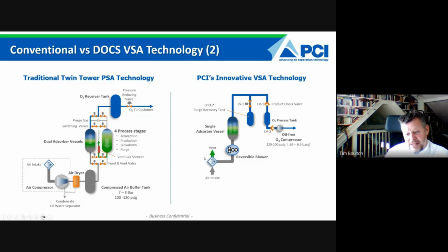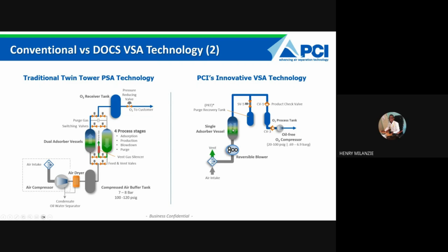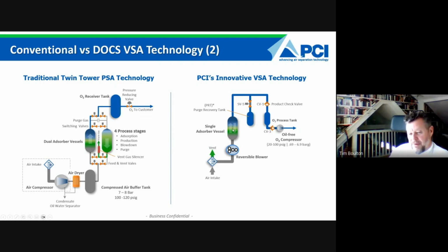The actual air compressor here is not a compressor, but a blower. All that means is that instead of taking a 7 bar intake pressure here, we are working at approximately a maximum of about 0.9 bar pressure. So the oxygen here is generated at 7 bar. In the VSA, it is generated at less than 1 bar pressure.